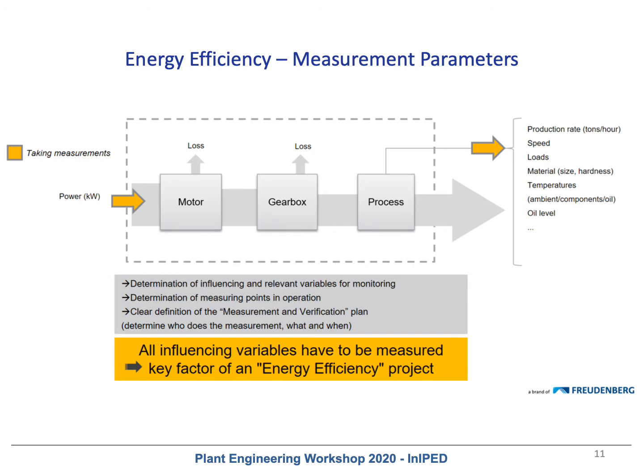Take, for example, the assembly and equipment shown in this picture. We would take measurement on the input power going into the electric motor that drives the gearbox in the process. And then, at the end of the process, we would monitor all the following parameters: the production rate, tons per hour, for example, the speed of the process, the loads, the material, the size and hardness of the particle, the temperatures, ambient temperature, the component temperature, the oil temperature, and also the oil level.